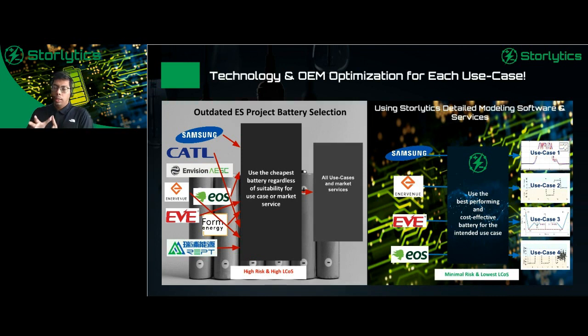When you're talking about choosing the right technology and OEM for your specific use case, right now in the current marketplace there's not a lot of focus on a specific use case. You typically get a requirement around 365 cycles per year. Now whether that's a deep discharge, energy arbitrage type of cycling, one cycle per day, or more like ancillary or market services where you're not doing a full cycle but a lot of intermittent cycles, all these have different impact on degradation and battery sizing. But right now the market is using very generic assumptions on the use case and then trying to choose the best.